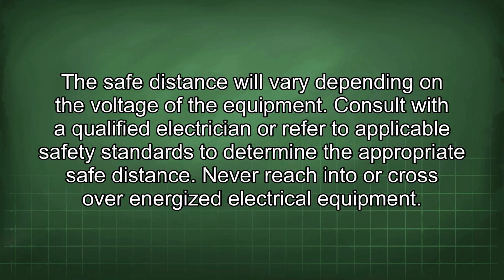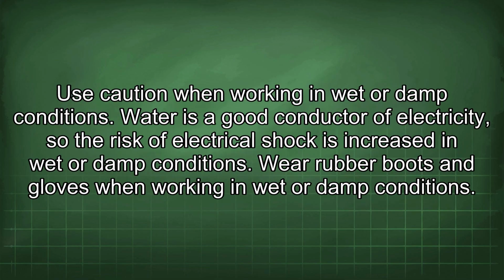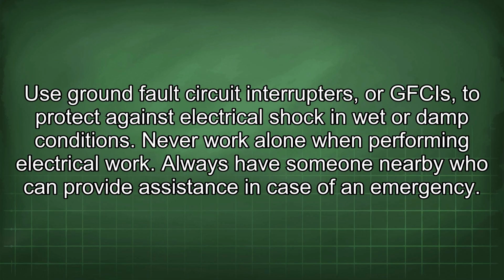Never reach into or cross over energized electrical equipment. Use caution when working in wet or damp conditions. Water is a good conductor of electricity, so the risk of electrical shock is increased in wet or damp conditions. Wear rubber boots and gloves when working in wet or damp conditions. Use ground fault circuit interrupters, or GFCIs, to protect against electrical shock in wet or damp conditions.